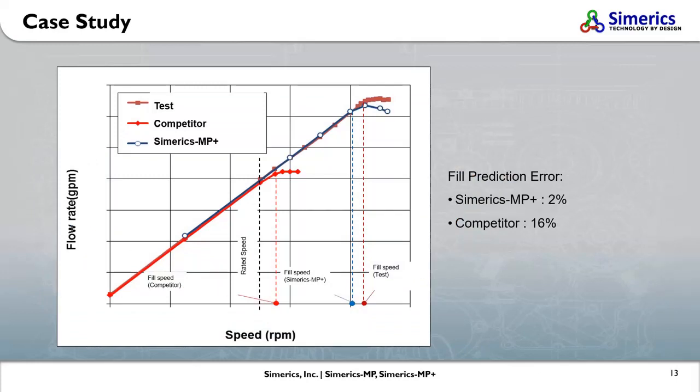Now let's look at a self-priming analysis, in which a pump's speed is increased until the flow rate curve starts to flatten due to cavitation. The brown red line denotes the Simerics MP Plus results, while the smaller red line denotes the results from another CFD tool. Simerics MP Plus prediction had an error of 2%, while the other CFD tool generated an error of 16%.